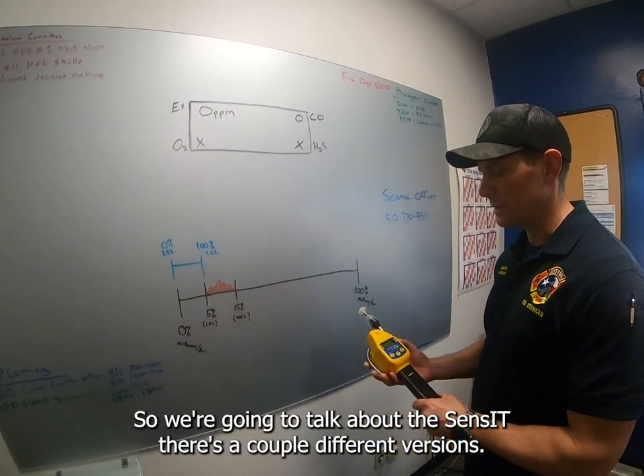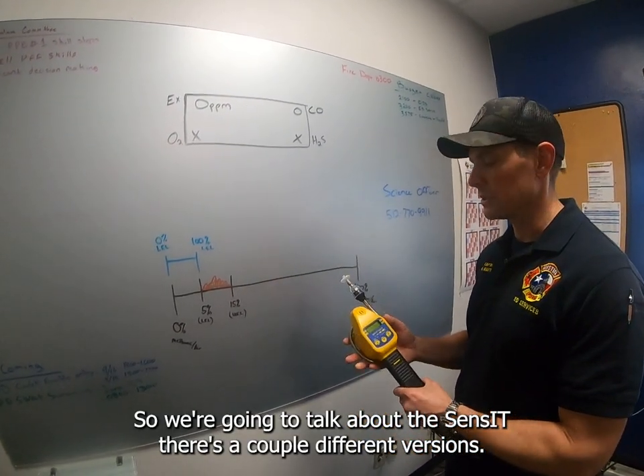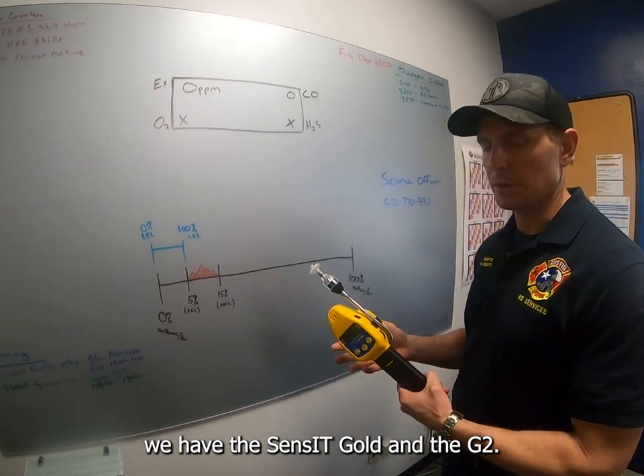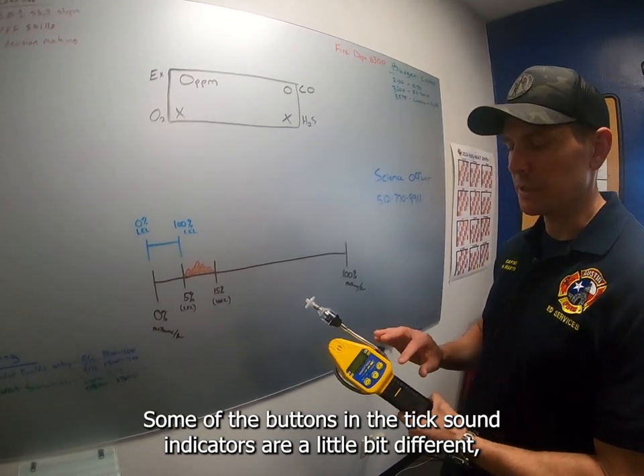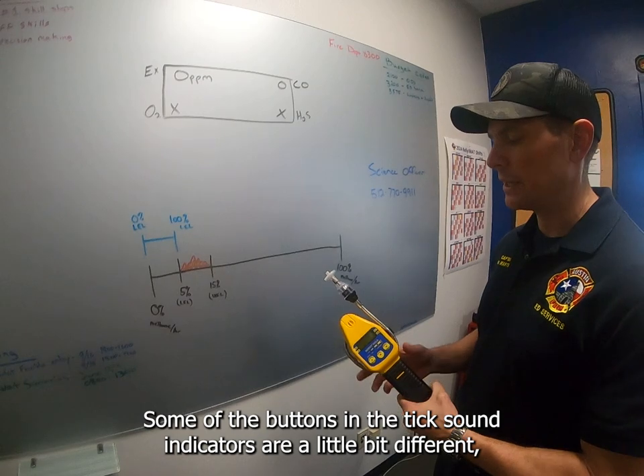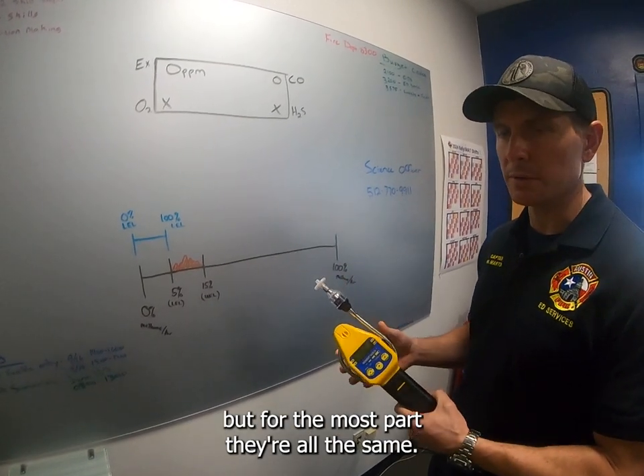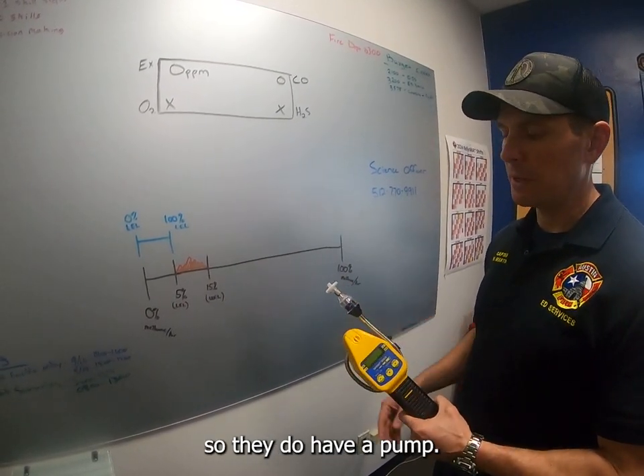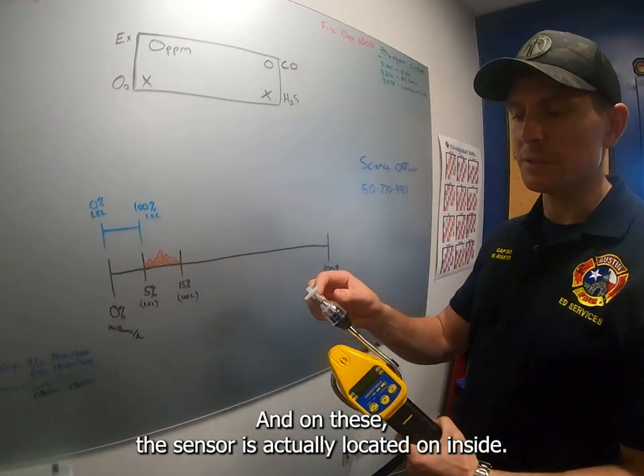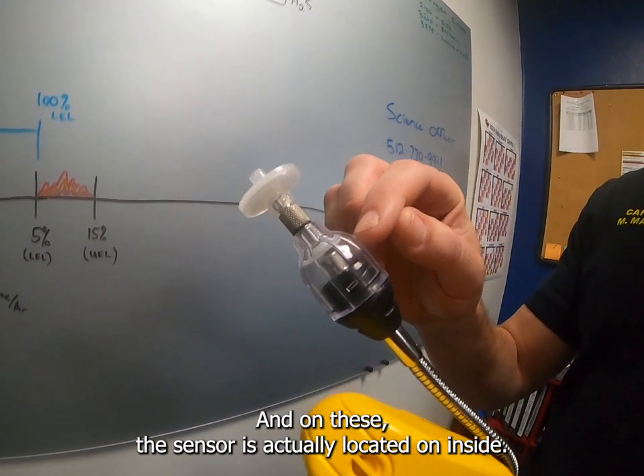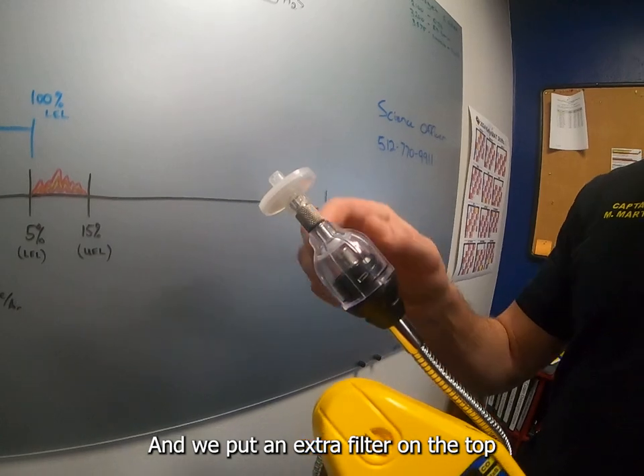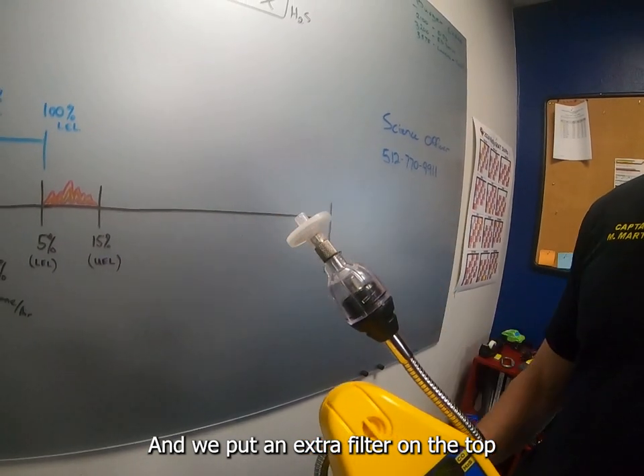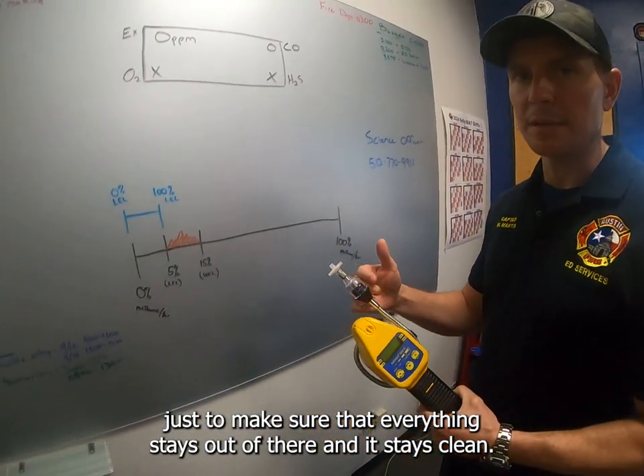So we're going to talk about the SensIT. There's a couple different versions. We have the SensIT Gold and the G2. Some of the buttons and the tick sound indicators are a little bit different, but for the most part, they're all the same. So they do have a pump, and on these, the sensor is actually located inside, and we put an extra filter on the top just to make sure that everything stays out of there and it stays clean.